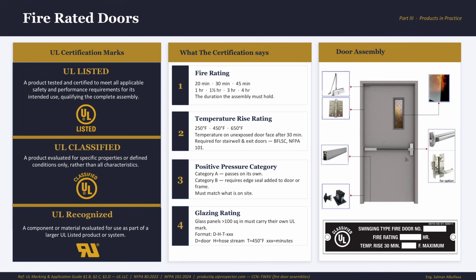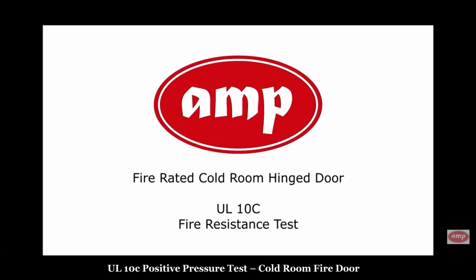And a door is not just a door. The door and assembly: every single component you see here, the closer, the hinges, the latch, the glazing, the seals, the panic bar, they make what a fire door is. And all of them must be tested together as one complete unit. I cannot merge them from different manufacturers, from different products and materials. They should all be tested together as one unit. And in the next slide, we're going to see a video about UL 10C fire resistance testing, about a fire-rated cold room hinge door.